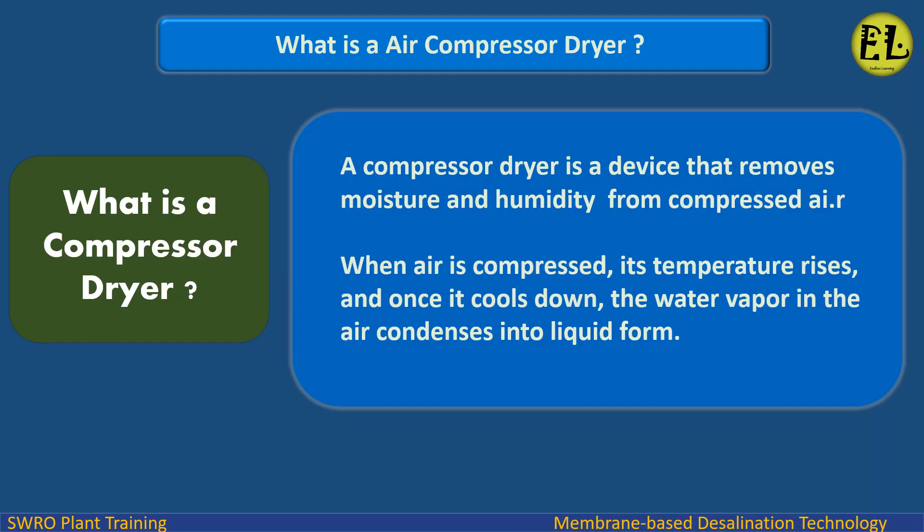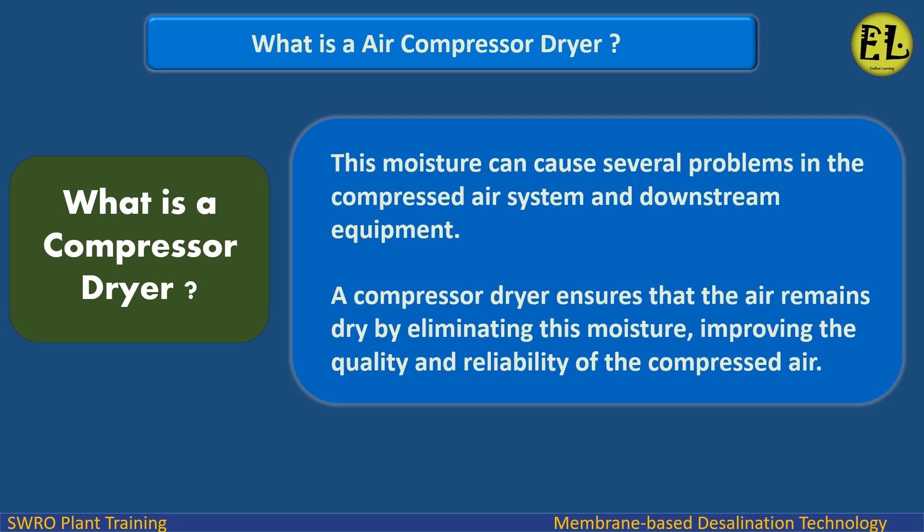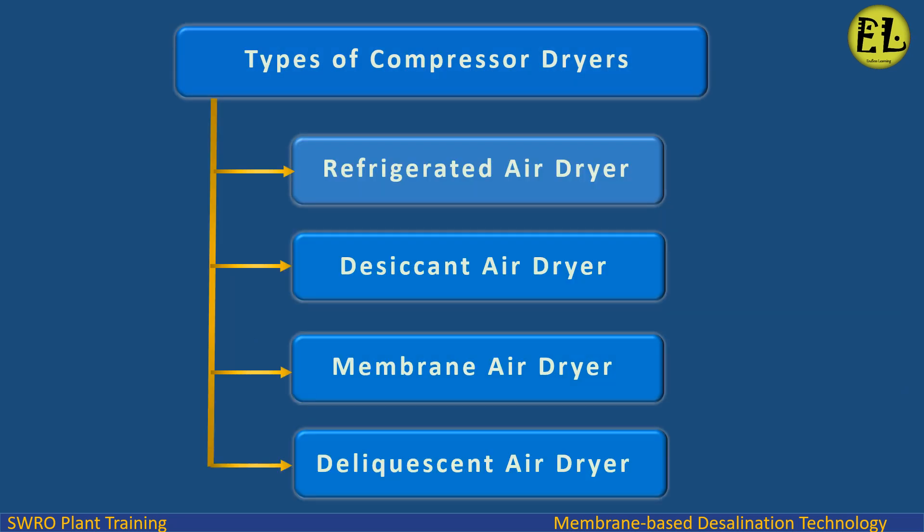What is a compressor dryer? A compressor dryer is a device that removes moisture and humidity from compressed air. When air is compressed, its temperature rises, and once it cools down, the water vapor in the air condenses into liquid form. This moisture can cause several problems in the compressed air system and downstream equipment. A compressor dryer ensures that the air remains dry by eliminating this moisture, improving the quality and reliability of the compressed air.